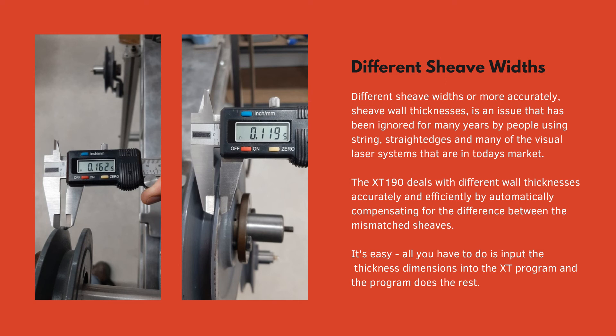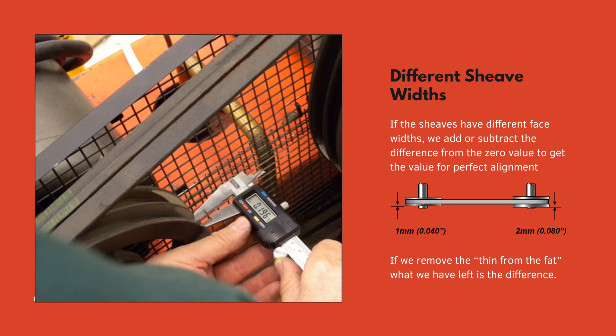Different sheave widths — more accurately sheave wall thicknesses — is an issue that has been ignored for many years by people using string, straight edges, and many of the visual laser systems on today's market. The XT190 deals with different wall thicknesses accurately and efficiently by automatically compensating for the difference between mismatched sheaves. All you have to do is input the thickness dimensions into the XT program and the program does the rest. If the sheaves have different face widths, you add or subtract the difference from the zero value to get the value for perfect alignment.